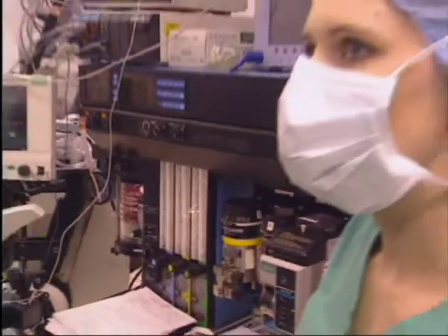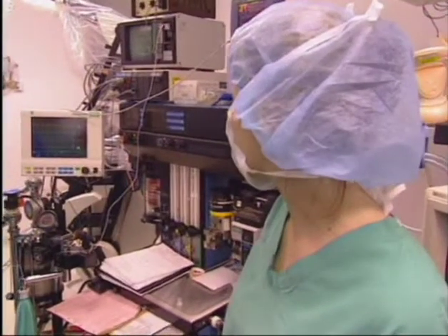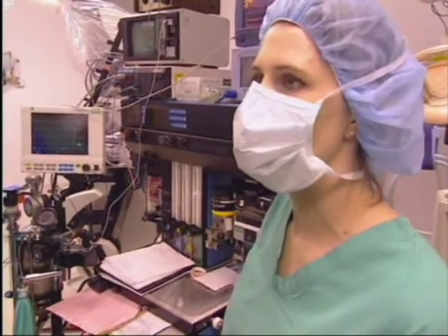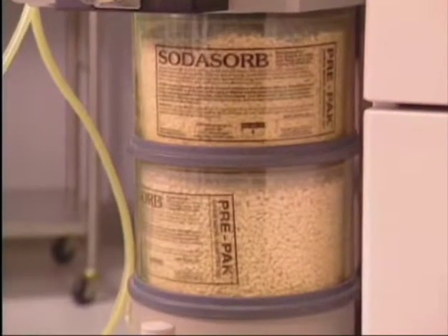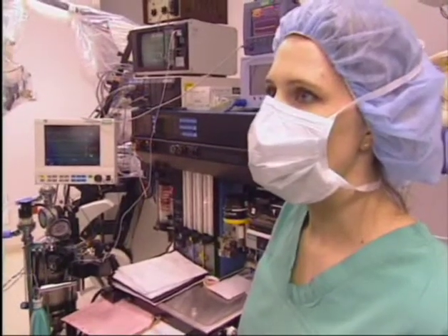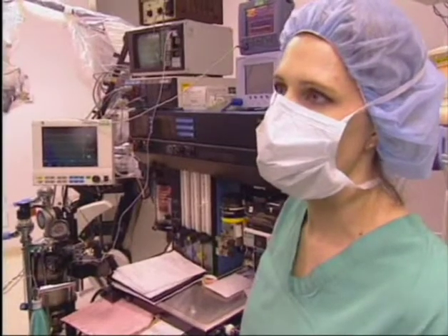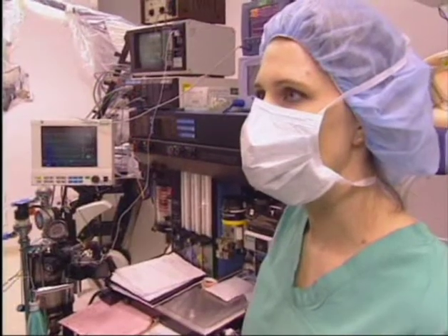Is there any risk from compound A under these circumstances? No, I would think that the levels of compound A that are actually being produced are still fairly low, that you won't see any renal injury. Okay, and why are the levels low? Because you have your high gas flows. And what does that do to the carbon dioxide that gets to the absorbent? Basically, it's decreasing the amount of carbon dioxide that actually gets to the absorbent, which helps, and a decreased amount of carbon dioxide decreases the temperature of the absorbent, which also decreases compound A production. So the temperature just doesn't get very high in the absorbent at this flow rate. Right.